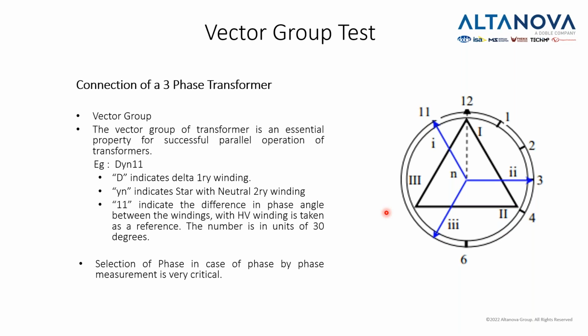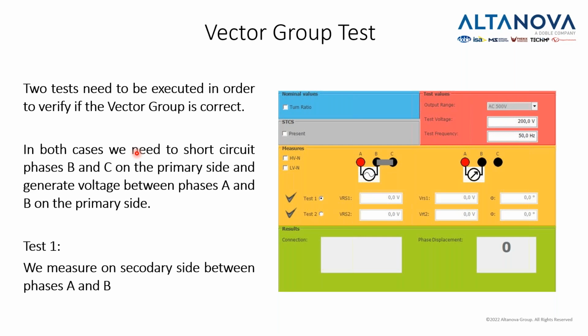Vector group is used so that we can do a successful parallel operation of transformers. So for example, DYN11 would mean that the first letter D denotes that we have a delta primary winding, and YN denotes that we have a star with neutral secondary winding. 11 is the number, it is a phase shift. Actually, it's this number multiplied by 30 degrees, which will tell us the phase shift between the primary and the secondary.